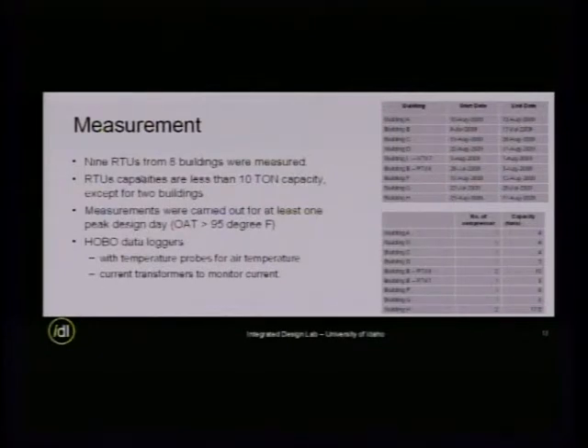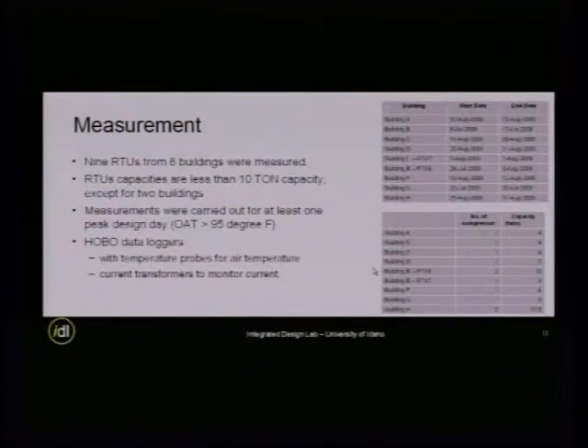We measured 9 RTUs, 9 units from 8 buildings. The RTU capacities are typically less than 10 tons, except for 2 buildings, exactly at 10 and 17, but the 17 ton unit actually has 2 compressors, so each of them is less than 10 tons. And then measurements were carried out. We went to the building and installed the equipment, and then we kept on measuring until we had at least one day where the temperature is above 95, which is the design day of Boise. And mind you, we don't have that many days of 95. For 8 buildings, we have practically 8 weeks, and then it's gone. So it's a very tight measurement schedule.